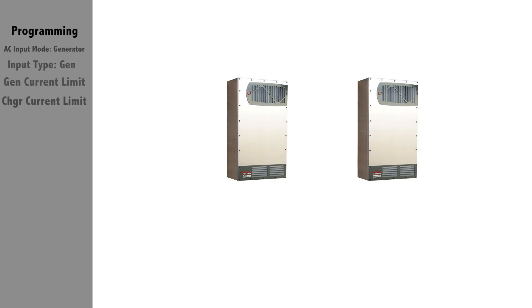For multiple stacked inverters, divide the total AC charge current by the amount of charger inverters used and program the master with the result. The master will operate the slaves with the setting to achieve the total charge current.